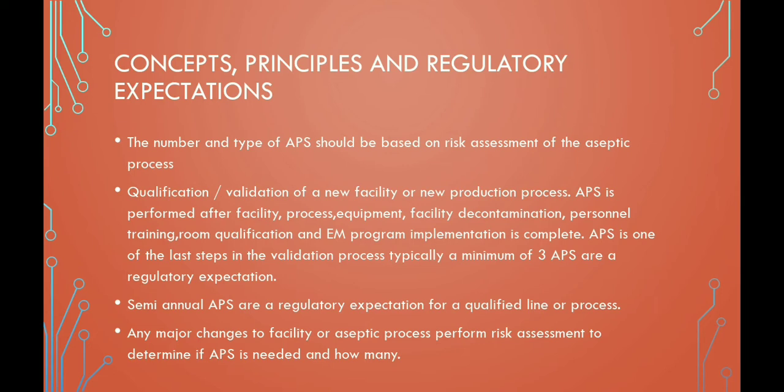For qualification or validation of a new facility or new production process, aseptic process simulation is performed after facility, process, equipment, and facility decontamination, personal training, room qualification, and environmental monitoring program implementation are complete. Aseptic process simulation is one of the last steps in the validation process. Typically a minimum of three aseptic process simulations are required by regulatory expectations.